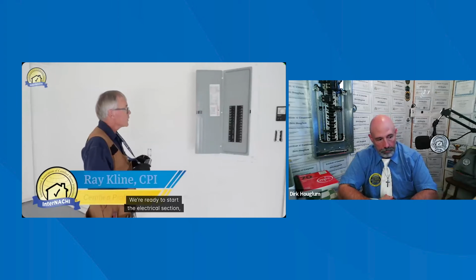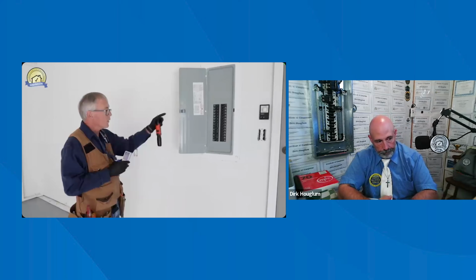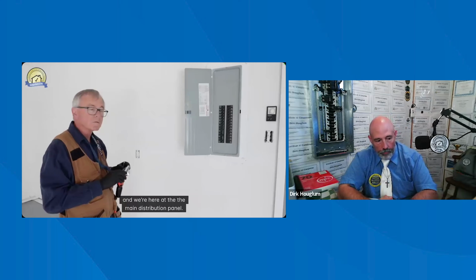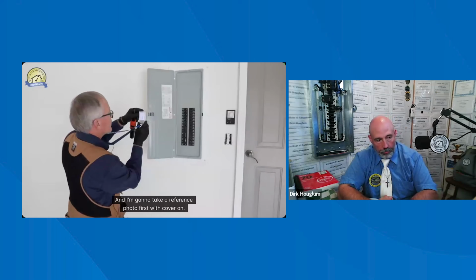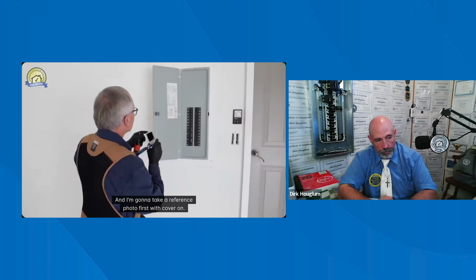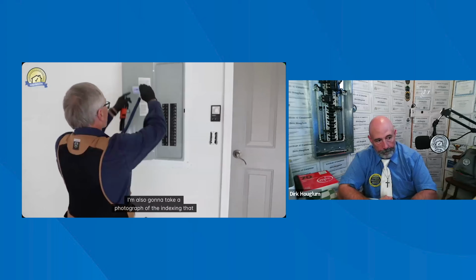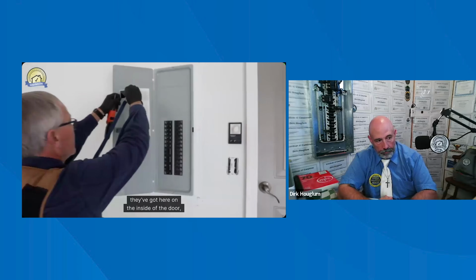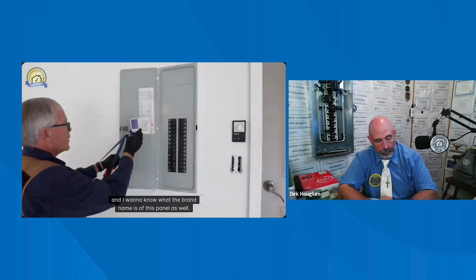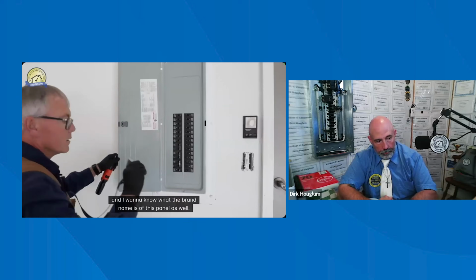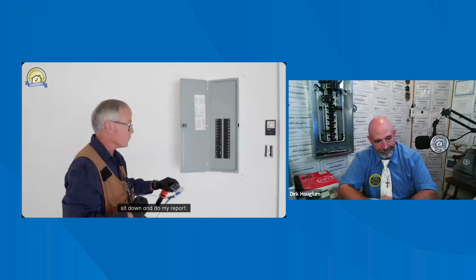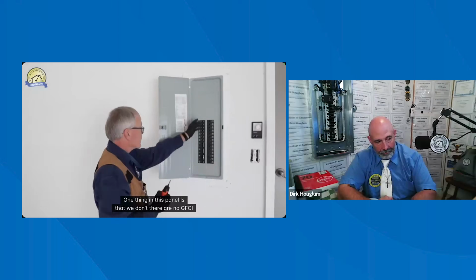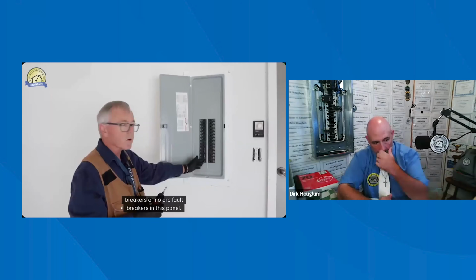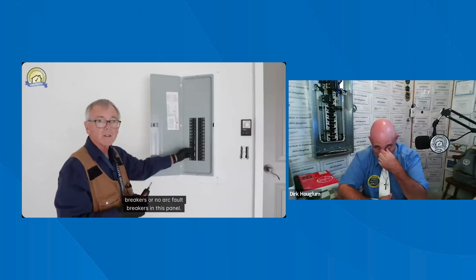Okay, we're ready to start the electrical section, which is 3.7 in the SOP. And we're here at the main distribution panel. I'm going to take a reference photo first with the cover on. I'm also going to take a photograph of the indexing that they've got here on the inside of the door. And I want to know what the brand name of this panel is as well. So I just took a picture of that so I remember it when I sit down and do my report. One thing in this panel is that there are no GFCI breakers or arc fault breakers in this panel.